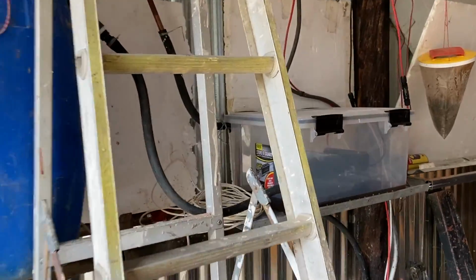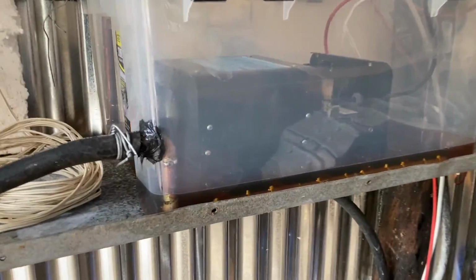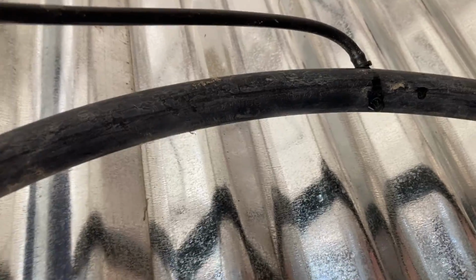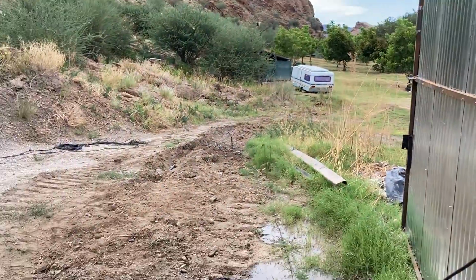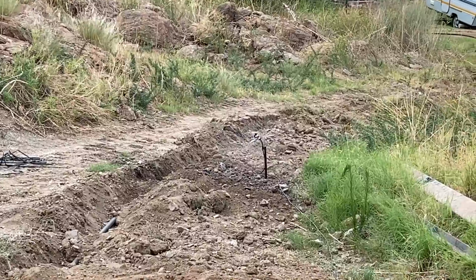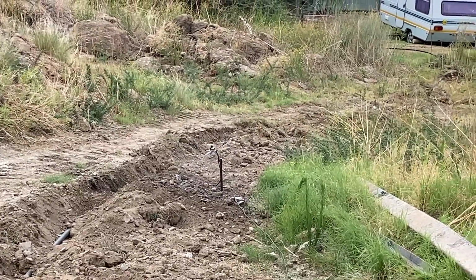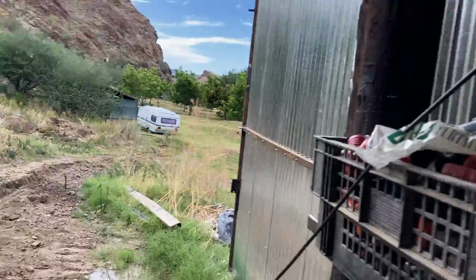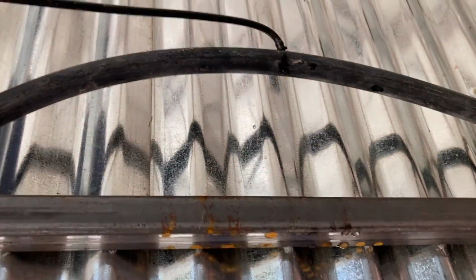One last thing, you want to avoid trapping air in this heat exchanger. Because it's lying horizontally, it could very easily get air trapped in there. So what I do to prevent that is, at the highest point, the supply line I loop upwards, and at the highest point I've put in a little outlet that goes to a little sprinkler you can see over there. In the morning when the system fires up and there's possibly a little bit of air in the line, the air should find its way out at that point and not go down into your heat exchanger.